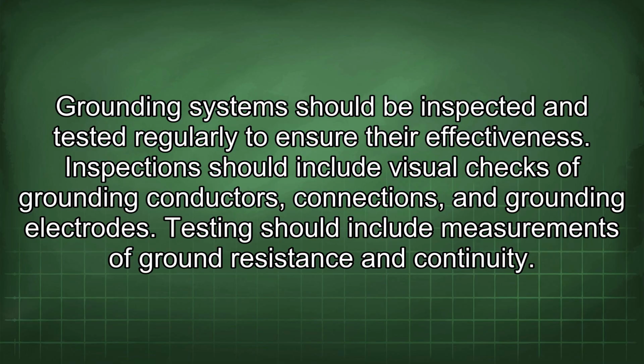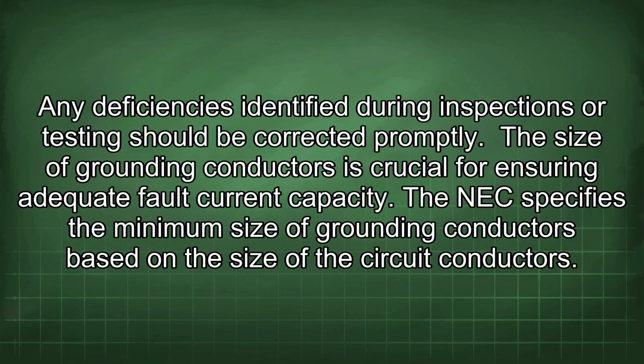Inspections should include visual checks of grounding conductors, connections, and grounding electrodes. Testing should include measurements of ground resistance and continuity. Any deficiencies identified during inspections or testing should be corrected promptly.